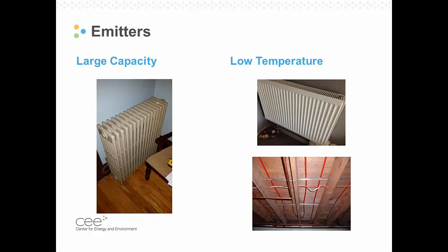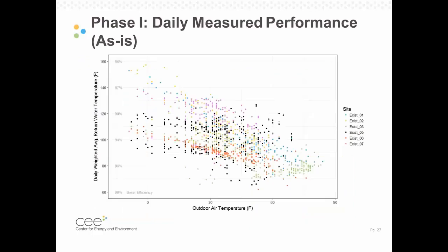The one type of emitter we've mentioned that you don't see on this slide is the fin tube baseboard emitter, and we didn't see many of those. Where we did, they tended to be towards the large capacity side, and we were able to run a lower than 180 degree water temperature through them. But there is a potential, depending on how the systems were designed, for those emitter types to fall outside of these categories. So just something to keep in mind there.